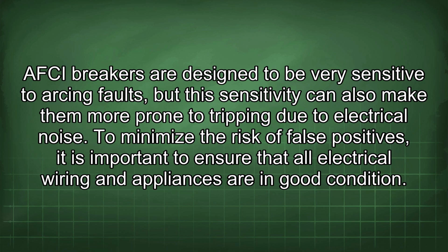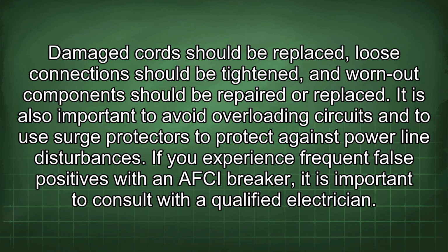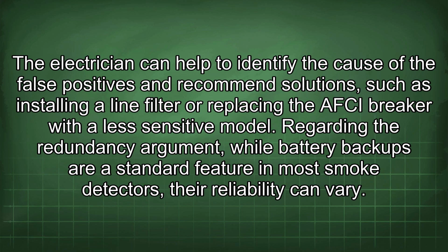To minimize the risk of false positives, it is important to ensure that all electrical wiring and appliances are in good condition. Damaged cords should be replaced, loose connections should be tightened, and worn-out components should be repaired or replaced. It is also important to avoid overloading circuits and to use surge protectors to protect against power line disturbances. If you experience frequent false positives with an AFCI breaker, it is important to consult with a qualified electrician. The electrician can help to identify the cause of the false positives and recommend solutions, such as installing a line filter or replacing the AFCI breaker with a less sensitive model.